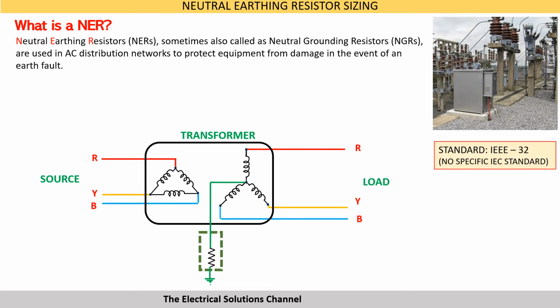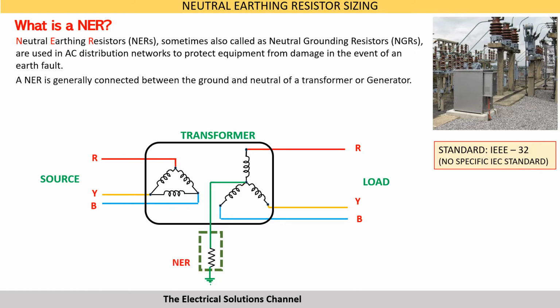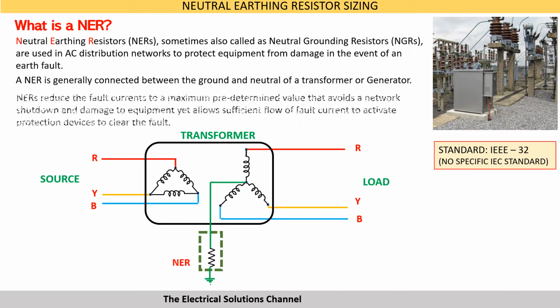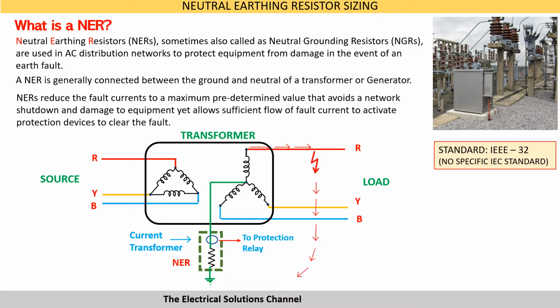Neutral earthing resistors, sometimes also called neutral grounding resistors, are used in AC distribution networks to protect equipment from damage in the event of an earth fault. A NER is generally connected between the ground and the neutral of a transformer or a generator. NERs reduce the fault currents to a maximum predetermined value that avoids a network shutdown and damage to the equipment, but allows sufficient flow of current to activate protection devices to clear the fault.